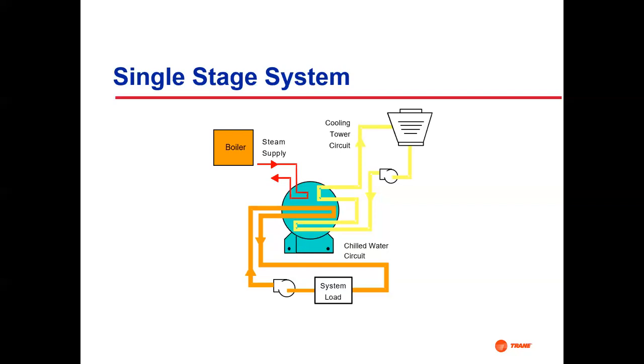Then we go to the condenser up here on the other side, where the water vapor comes over. It's 95 to 103. We've got 103 going back to the tower. Water falls down on the tower. We've got a fan here sucking air up that has probably a wet bulb temperature design of 78. That causes some of this water to evaporate. That cools down the flow, and we fall out at 85 and keep going around in a circle.